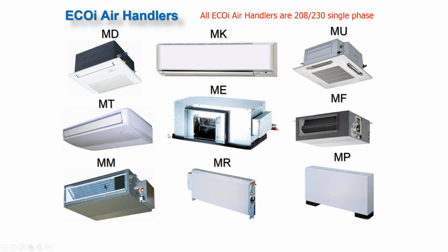In the middle here is our ME indoor unit. This is our high static concealed ducted unit, suitable for long duct runs. It's also capable of a 0.7 external static pressure. So this has a big fan in it. So if you wanted to put a good amount of ductwork on this, you can do that. Over here is our MF unit. This is our medium static concealed ducted unit, capable of a 0.6 external static pressure. This is the most popular unit for engineers and architects installing in New York City, in new office buildings or new buildings where aesthetics are a big deal. Architects like this unit the best because it is ducted. You can't see it.